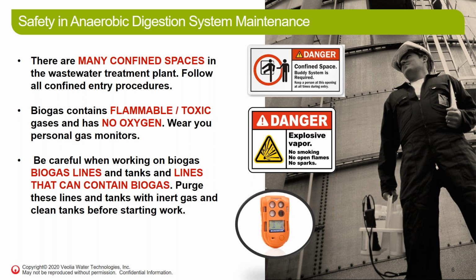The biogas, as you know, it could be explosive. It's natural gas. So although you need three things to make it explode, which is the fuel, which is your methane, you need oxygen and a source of ignition. You usually only have one of those, but you've got to be careful. You don't want to blow yourself up. And also the biogas contains hydrogen sulfide, which is very toxic. A lot of people don't realize that even the anaerobic effluent lines can contain biogas. So you have to be careful with working on those lines too. We also always recommend that you wear your H2S monitor so you know when you might have a biogas leak.